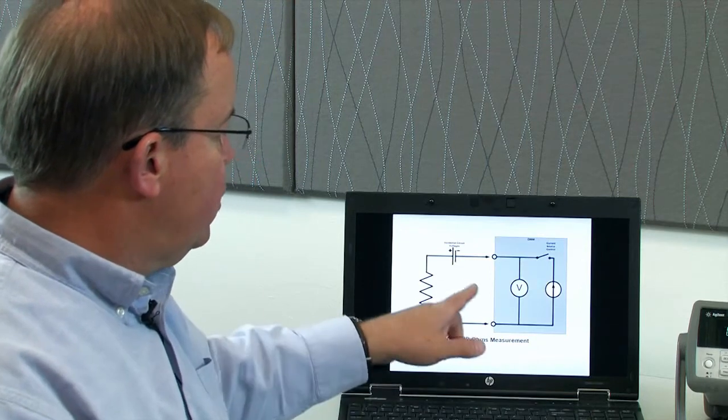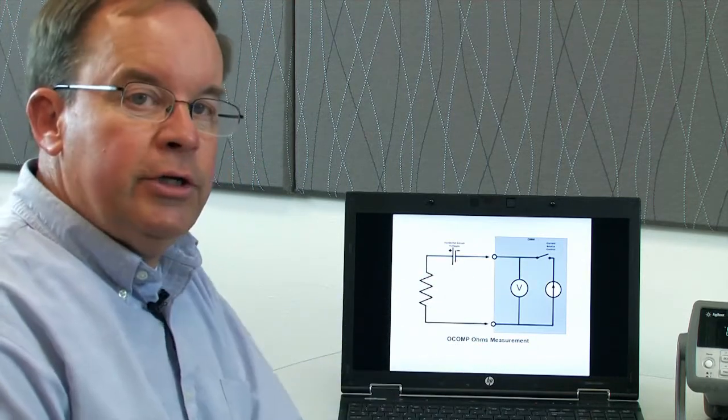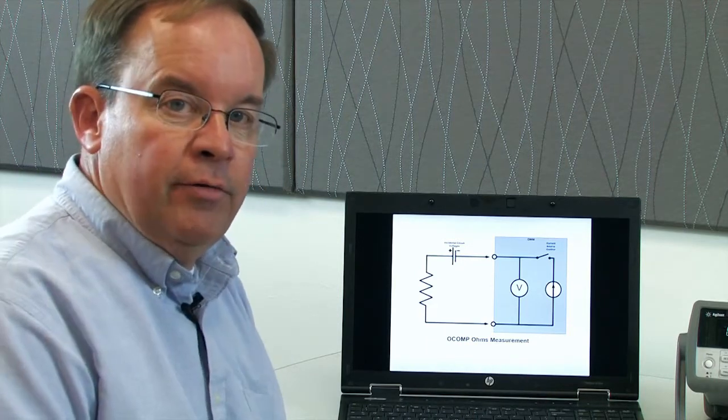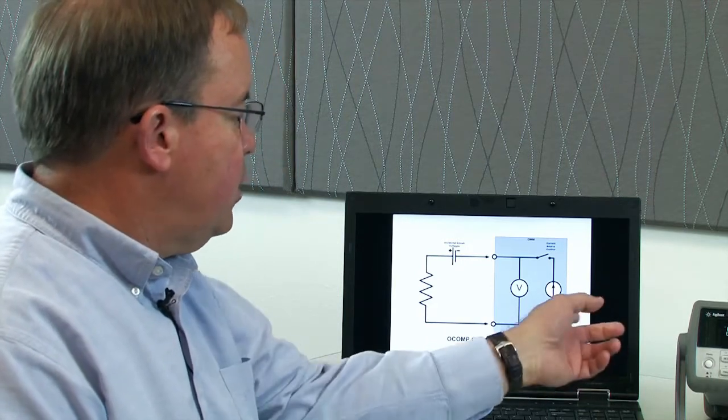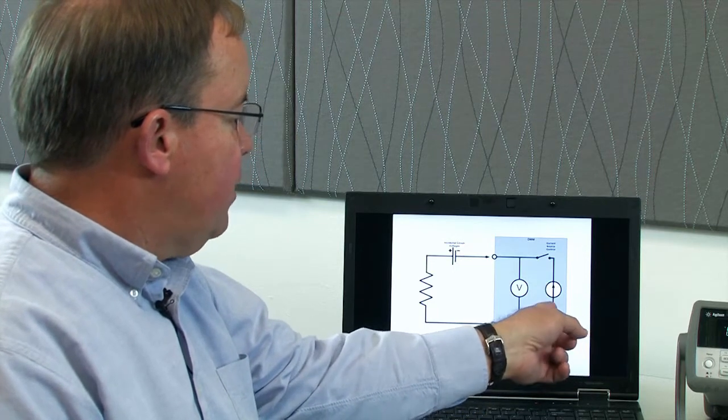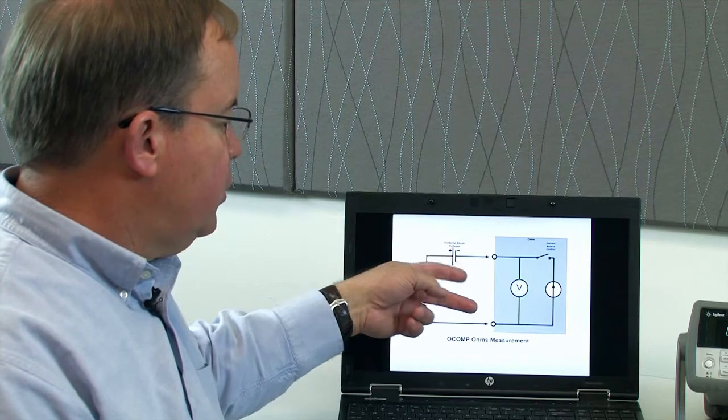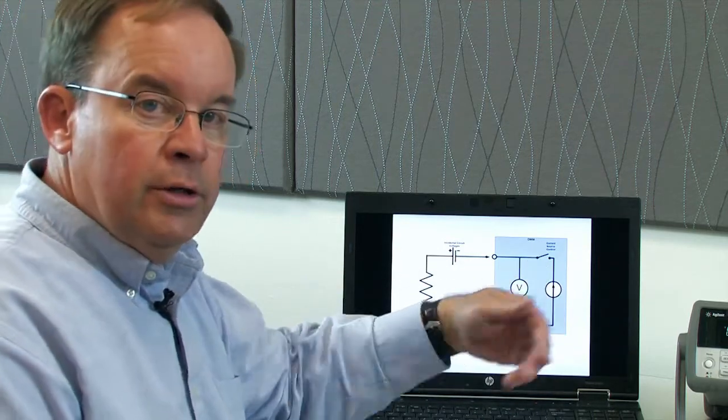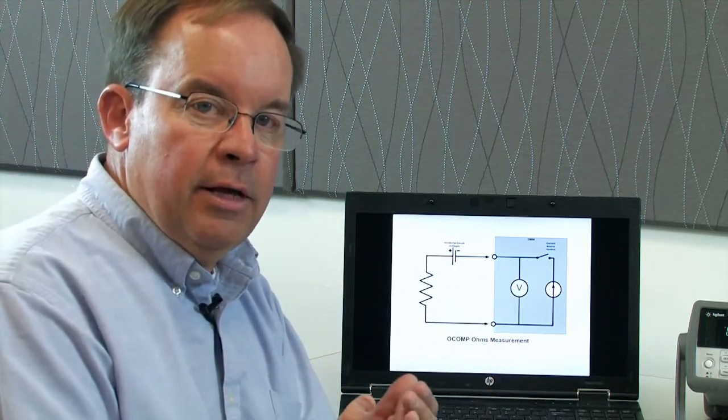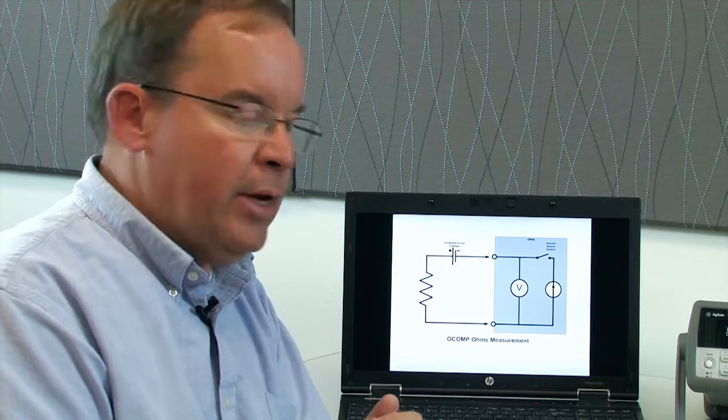Here's an example of a circuit in which we have some incidental voltages that have been added to the resistor itself. These may be very hard to get rid of in your actual measurement. So the digital multimeter then is able to switch off the current source, make a measurement of these incidental voltages, turn on the current source, and make a normal ohms resistance measurement, and then subtract the two and give you a very accurate measurement.